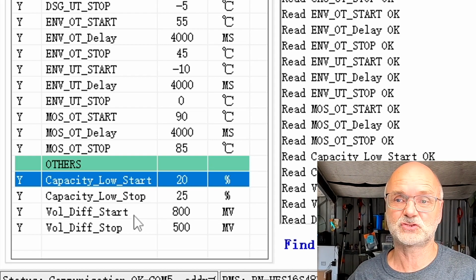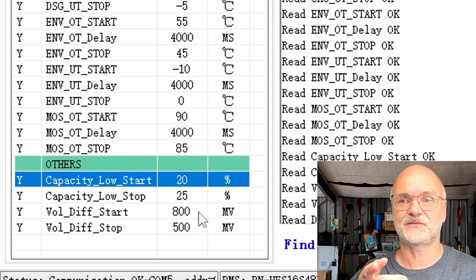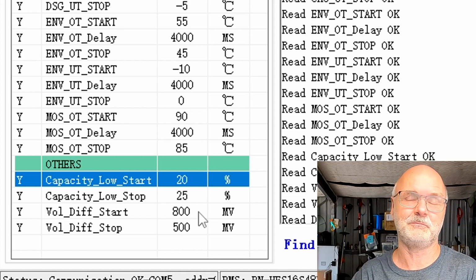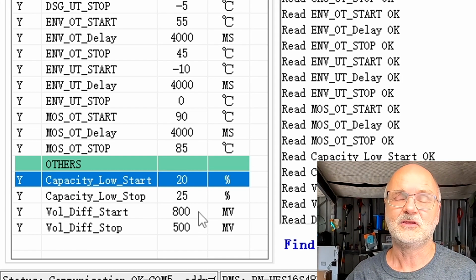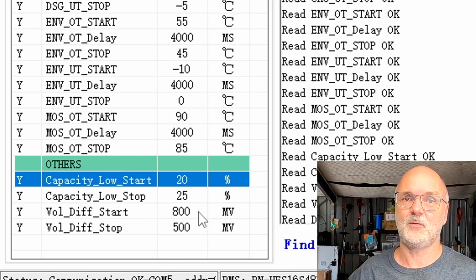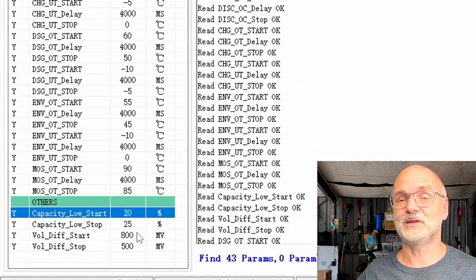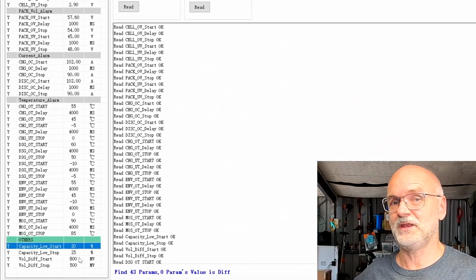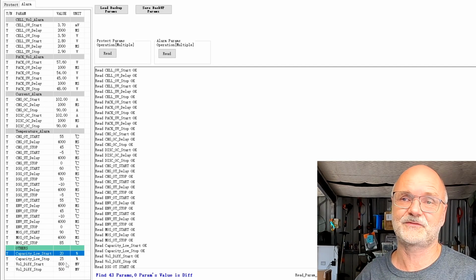We also have a voltage difference alarm. This triggers when the deviation across all 16 cells goes above 800 millivolts, as set here. You'll get an alarm telling you something is wrong with your battery. These are pretty much the standard parameters already programmed on the BMS.